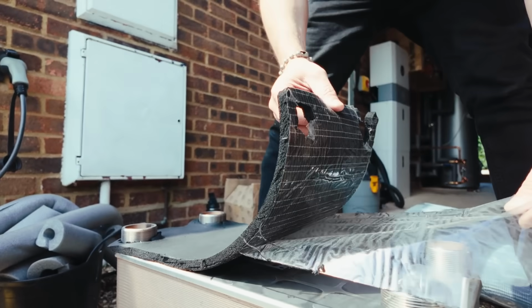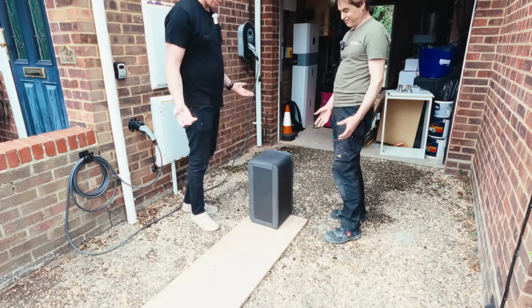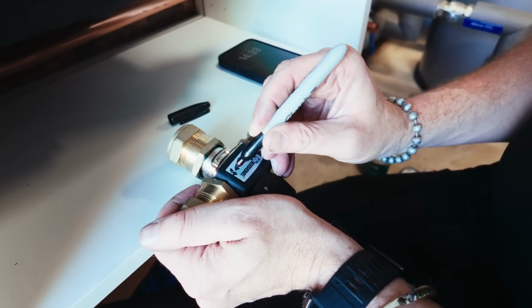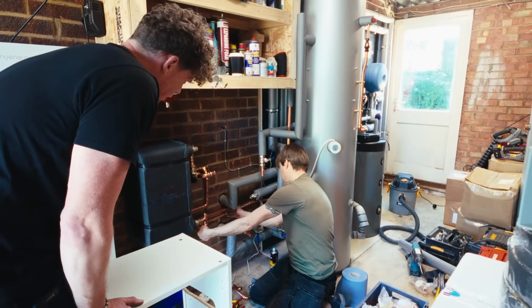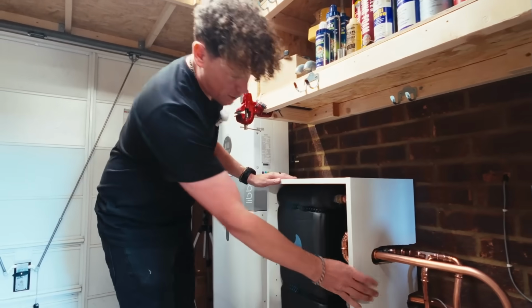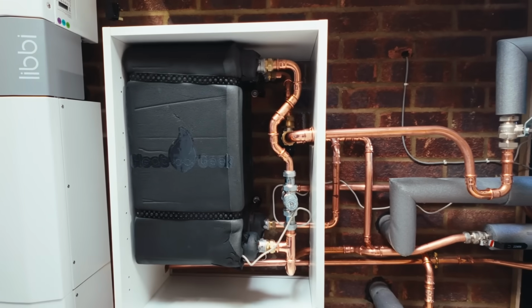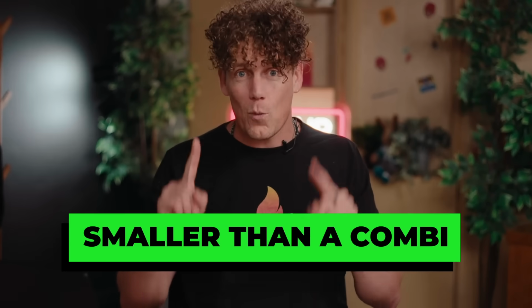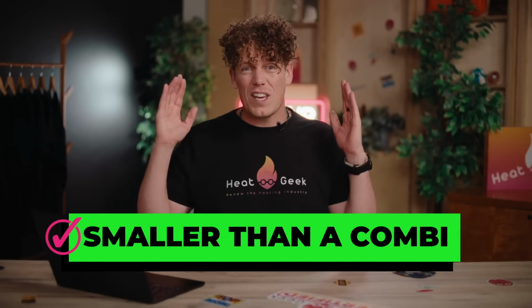As you can see, we fully insulated this in Armaflex to keep the heat in, installed the 2 blending valves to control the heat generation, and managed to easily fit this in a 300 by 400 millimeter cupboard, and even had room to spare. Only the smallest combi boilers on the market would just fit into this space, so objective number 1 was a success. We just needed to see if this was actually going to work.